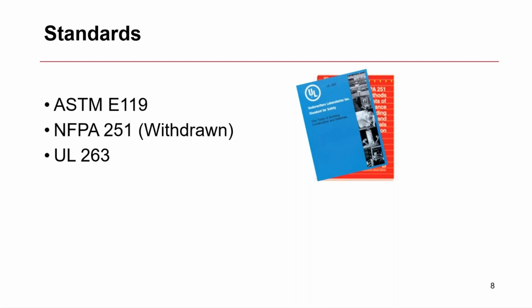I've noted here that NFPA 251 has been withdrawn, but the reason I maintain it on this slide is the fact that CMS requires healthcare facilities to comply with the 2012 edition of the Life Safety Code. That edition of the Life Safety Code still references NFPA 251. So until that edition of the code is no longer in use, I keep this reference to 251 on the slides, but just keep in mind that those 3 standards are all one and the same.